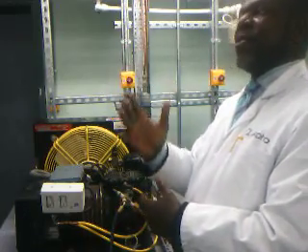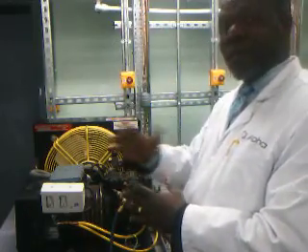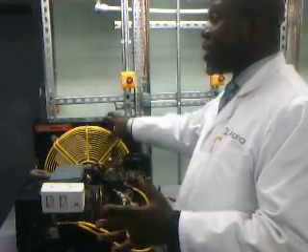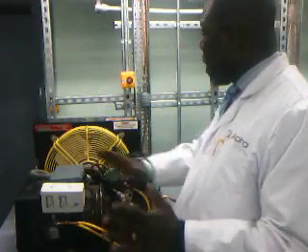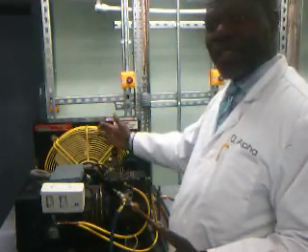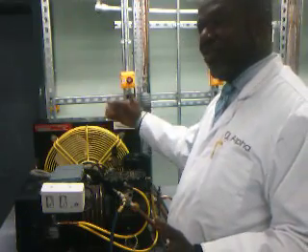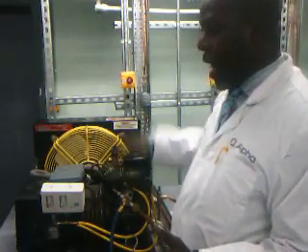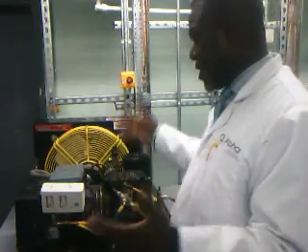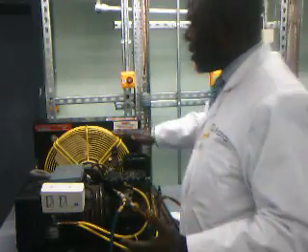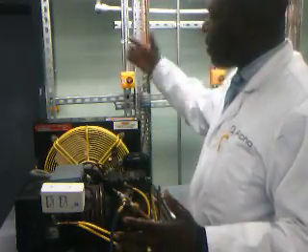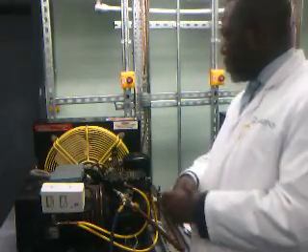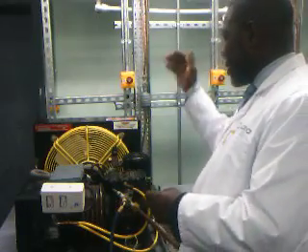If it's above it, say you have 10, 12 degrees of subcooling, that means the condenser is overcondensing, and it means you have too much liquid in the condenser. It could be that you have, say, overcharged the system slightly, not to the level where it will affect the compressor, because overcharge can create high head pressure. Pressure will increase in the condenser, but then you are at a stage where that overcharge is causing overcondensation. Too much liquid is going into the condenser.